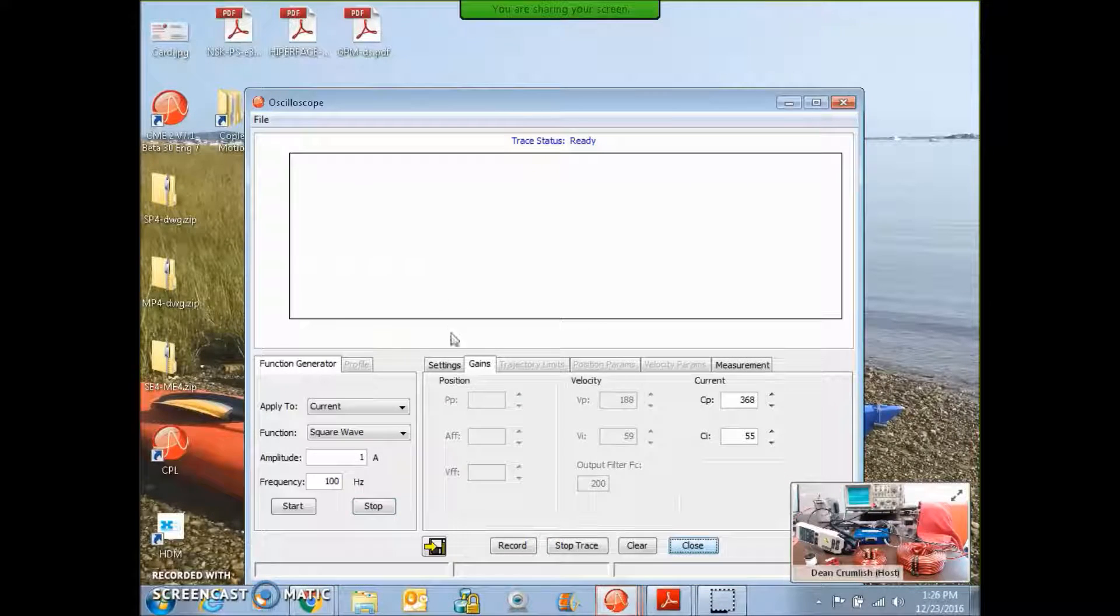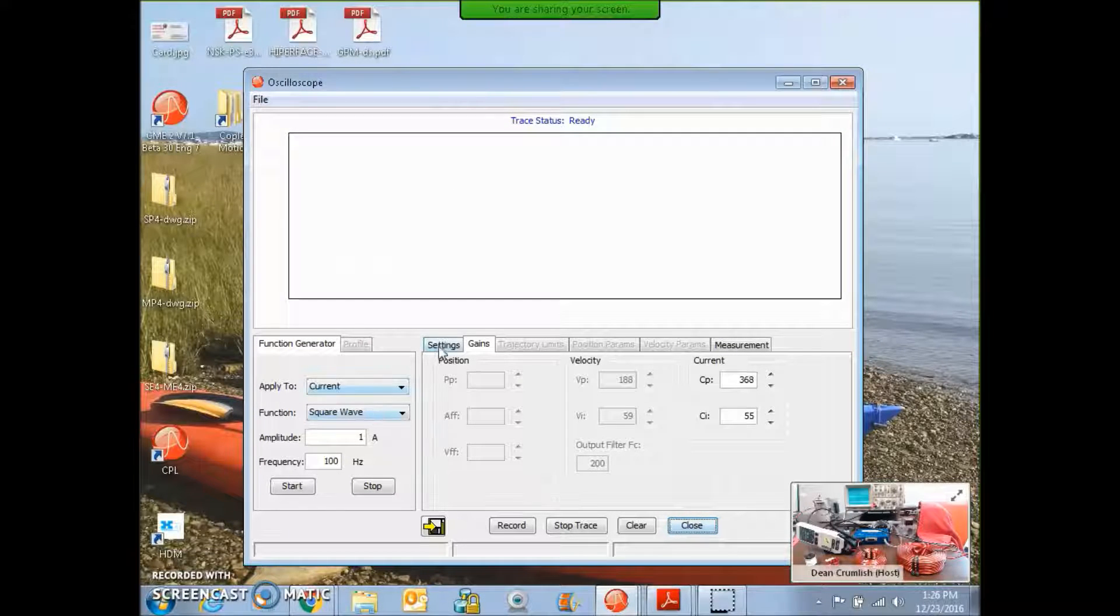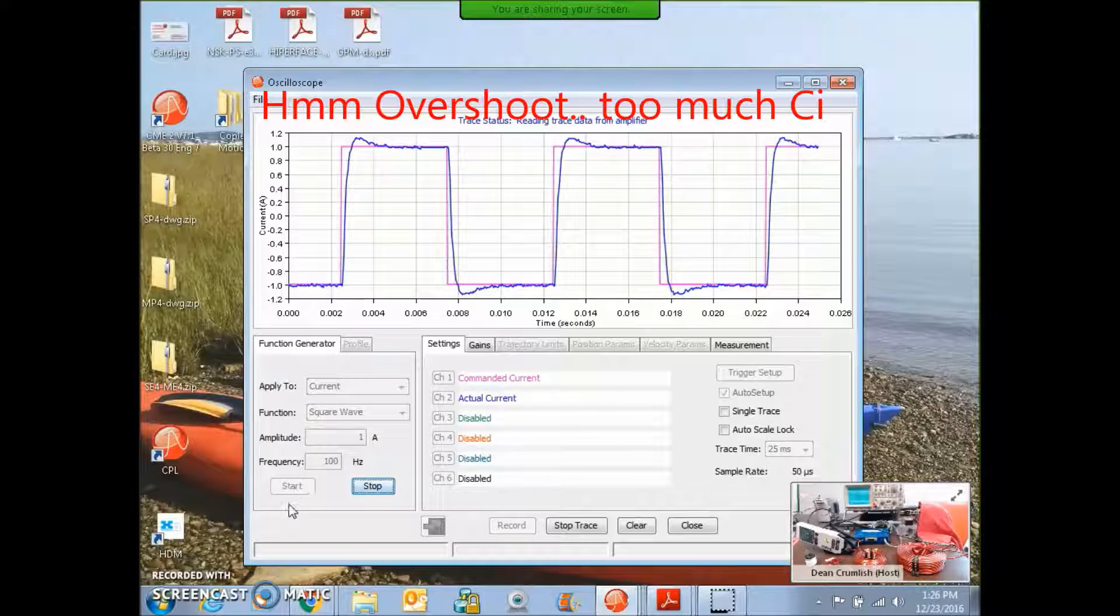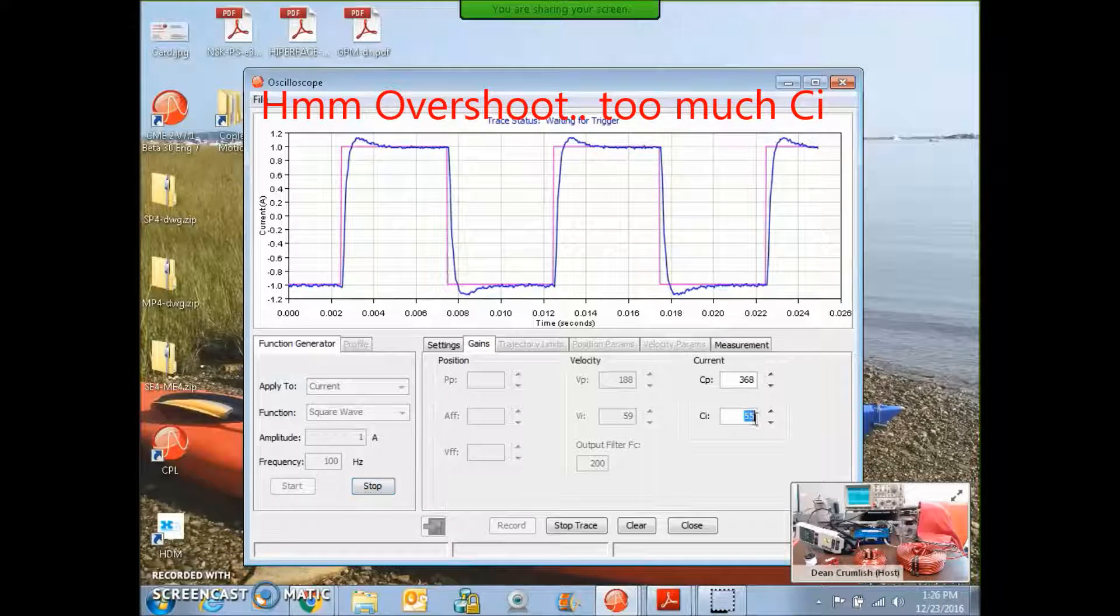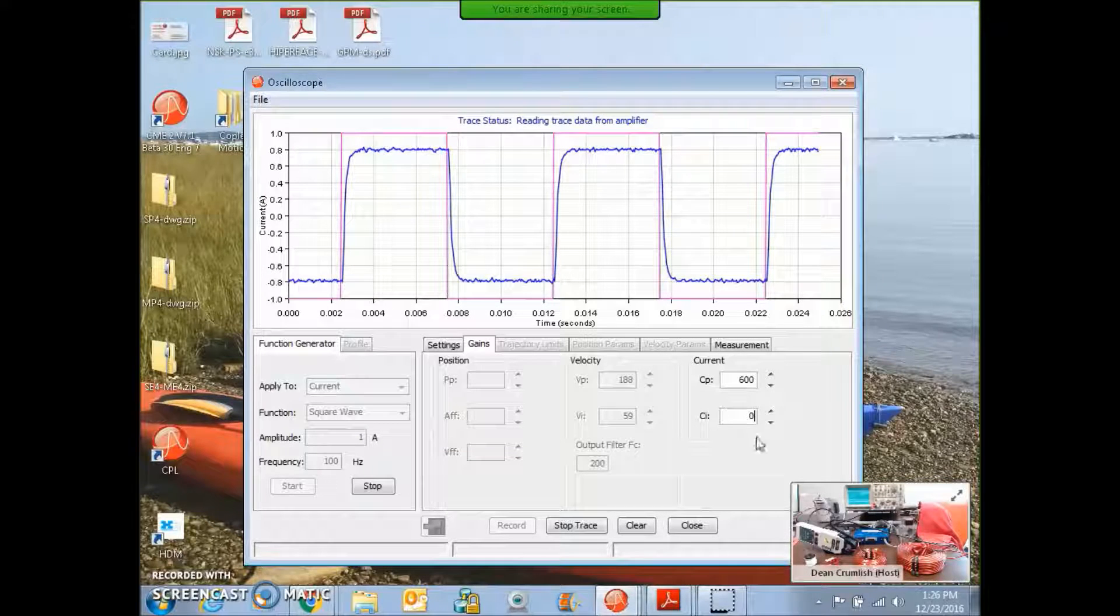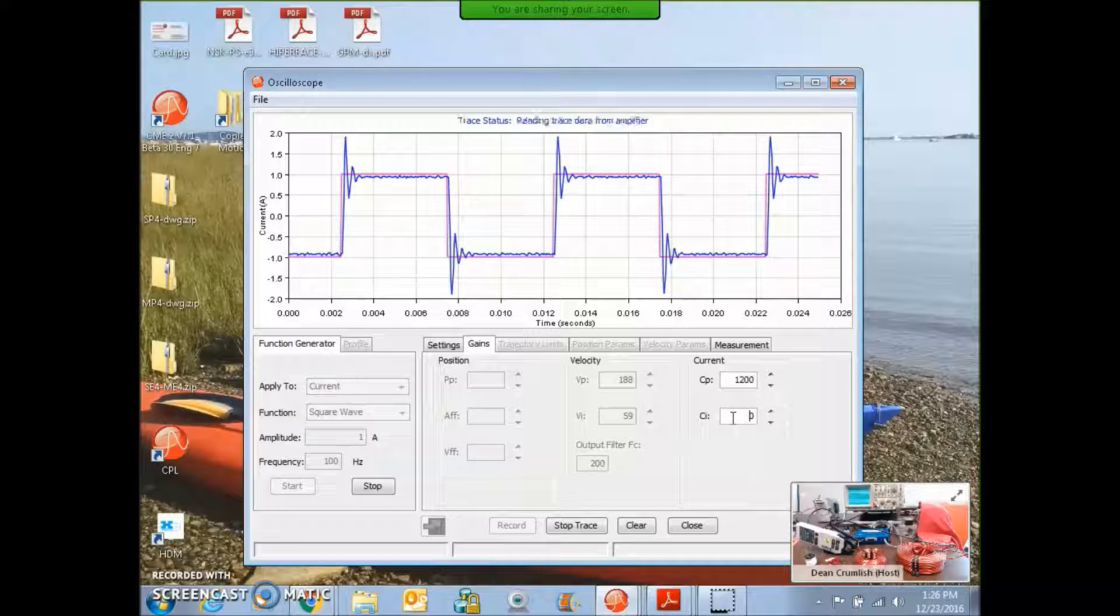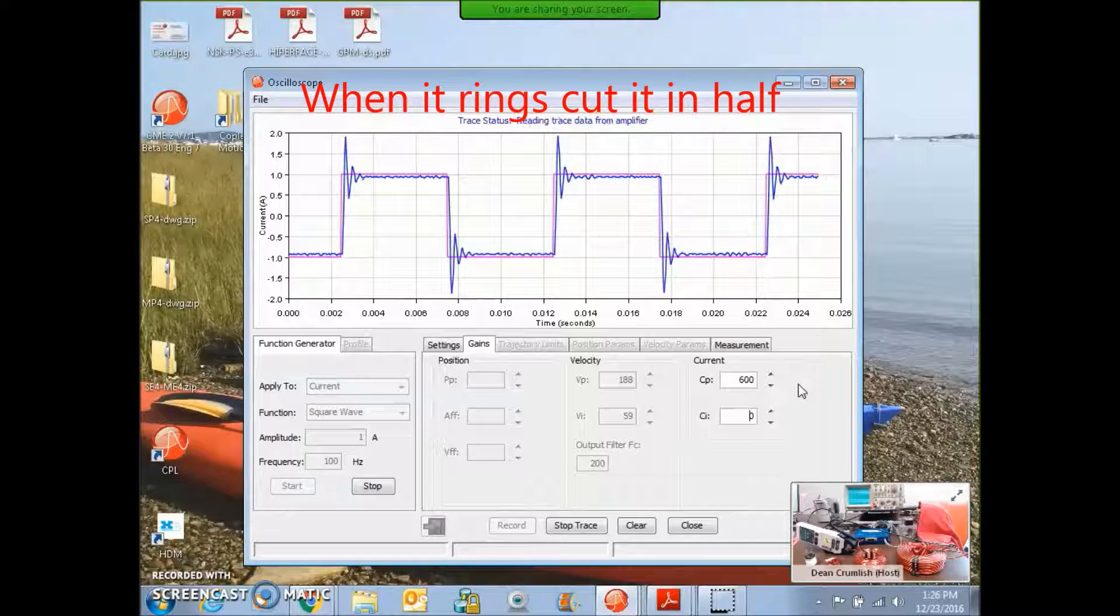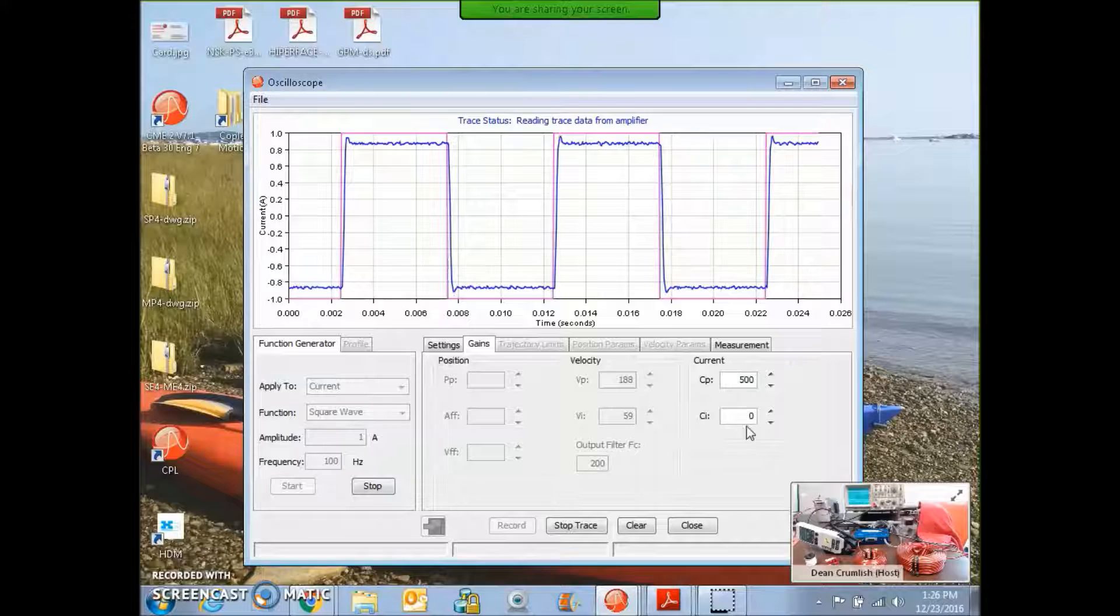I like to do my own tuning. So I use the CME2 scope, function generator, apply to current, auto setup checkbox and hit start. Real easy to get going. I see a little integral overshoot there, but let's take a look at the gains. Integral gets set to zero. We shoot for the P term. Too much proportional gain. I double it every time. And you see some overshoot. There's a little bit of overshoot. Let's just make it excessive. There's ringing there. So too much current loop gain. Cut it in half. Bring that value back down to 600. It's a little ringy. I can knock it down a little bit. Let's give it 500.